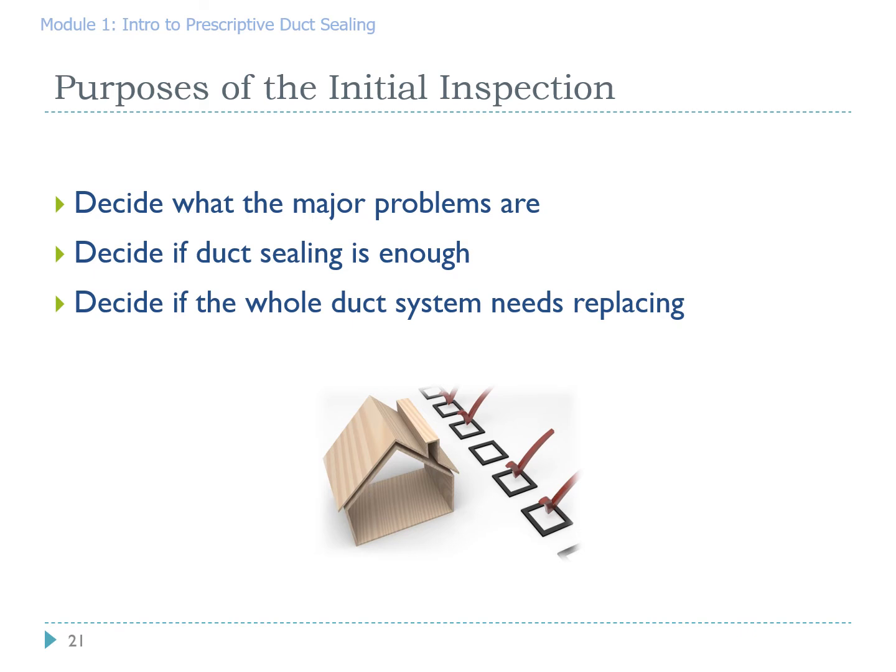If the duct system is in really pathetic condition, rusted out, torn up, rodent infested, it might be a good idea to bid the whole duct system and replace it. It's not eligible under the program. However, it is a good idea and the homeowner will get value from it.